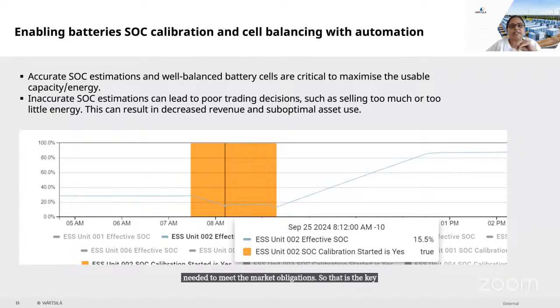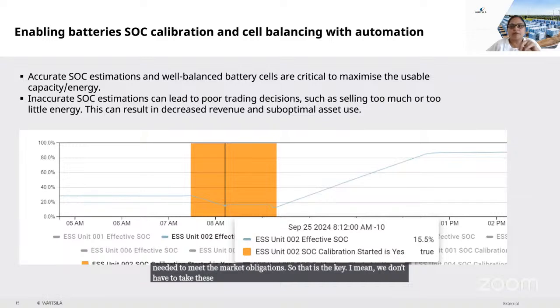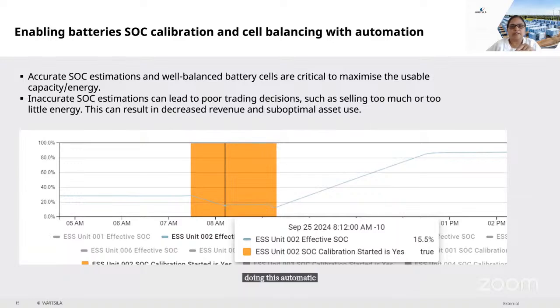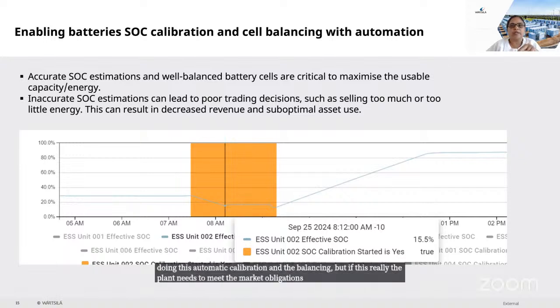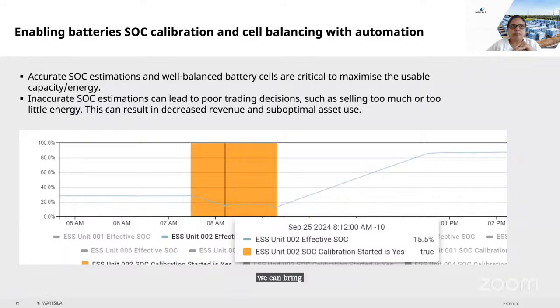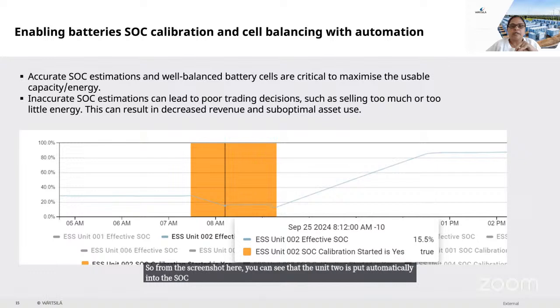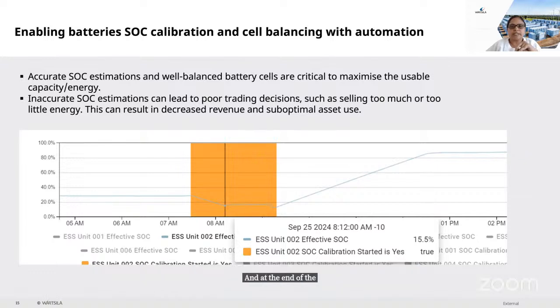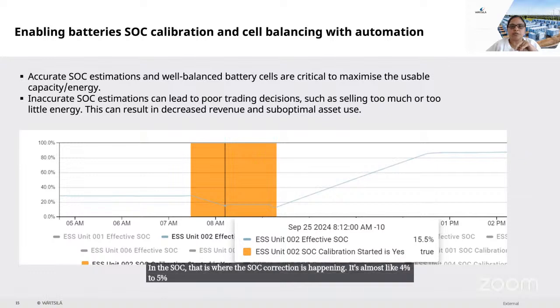We don't have to take these units away from the market. They are available while doing this automatic calibration and balancing. But if the plant really needs to meet the market obligations and these units are needed, we can bring them back in. From the screenshot here, you can see that unit 2 is put automatically into the SOC calibration. At the end of the calibration, you can see a dip in the SOC. That is where the SOC correction is happening. It's almost 4 to 5%, which is not negligible.